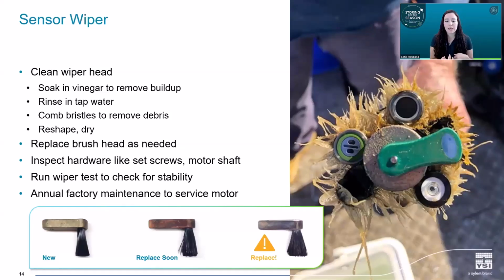And then also inspect the wiper hardware, anything you can access like set screws and the motor shaft. Don't try to take the wiper apart yourself. You're going to want to send it in annually or so for factory maintenance. That way they can take care of the motor and all the internal seals. And after you inspect everything on your wiper, you can run a wiper test, and that'll help check for stability and make sure that the brush is parking in the correct place and not over a sensor.